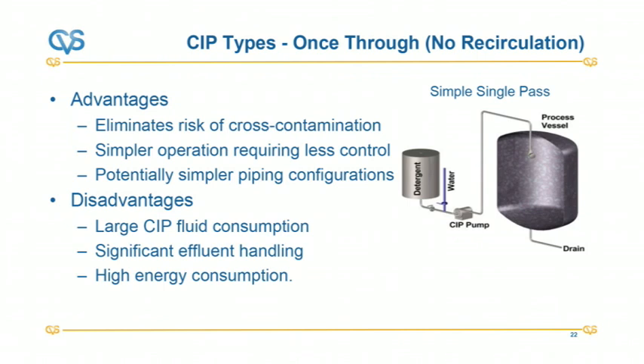Now, CIPs, there are generally three types. There's probably the most energy inefficient and the worst case for use of chemical agents. And this is basically a once-through system. So we basically have our detergent, and we may have a mixing process that mixes it in line. We have a clean-in-place pump that sprays through a spray nozzle, sprays the inside of the vessel, and then we run it to drain. So it just runs through. And then basically for the final rinse, we do it with just water to make sure we take the detergent out.